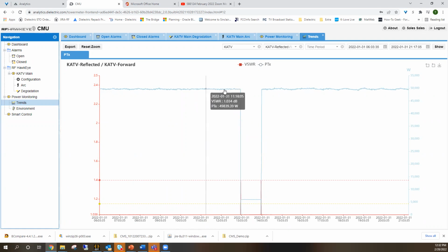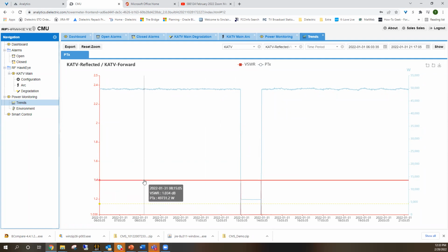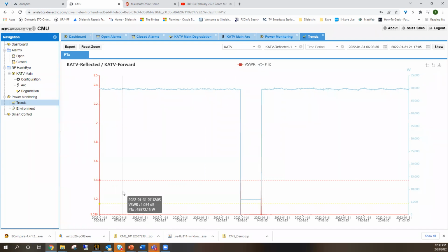And so it tells you your forward power. There was a dip. And then it showed when it came back up. And then the corresponding VSWR is the red line. And here are the set thresholds for that. So you can have a VSWR alarm, you can have a degradation alarm, you can have arc alarms.